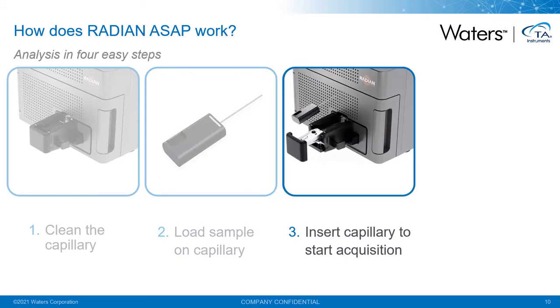Once you have your sample on the capillary, you place the holder and capillary into the loader on the front of the instrument. This will automatically start the acquisition. The instrument will acquire a background spectrum for a short while, and then a written instruction in the software and from the LEDs on the front of the instrument will inform you when to push the sample loader forwards into the instrument. If you have a temperature ramp or step temperature profile set up, this will automatically start when you push the sample in.